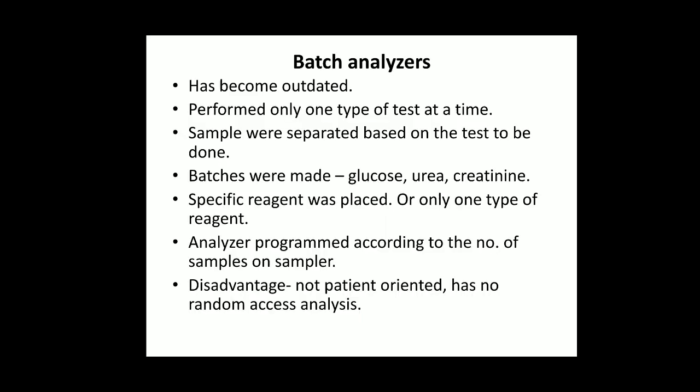The batch analyzer has become outdated. Only one particular test at a time can be done, and samples must be divided batch-wise — all samples for glucose are kept separately in a batch, analyzed first, then the next batch is processed. This is tedious, it is not being used now, and it is not patient-oriented.